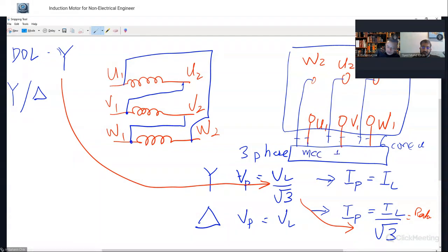Inside this MCC, there are contactors that when starting, connect the motor in star. Then when it runs, it shifts to delta. It uses contactors plus timer. For example, when you start, after a certain period of time, after a few seconds, then you switch to delta. This type of starter is being done to reduce the starting current of the motor.